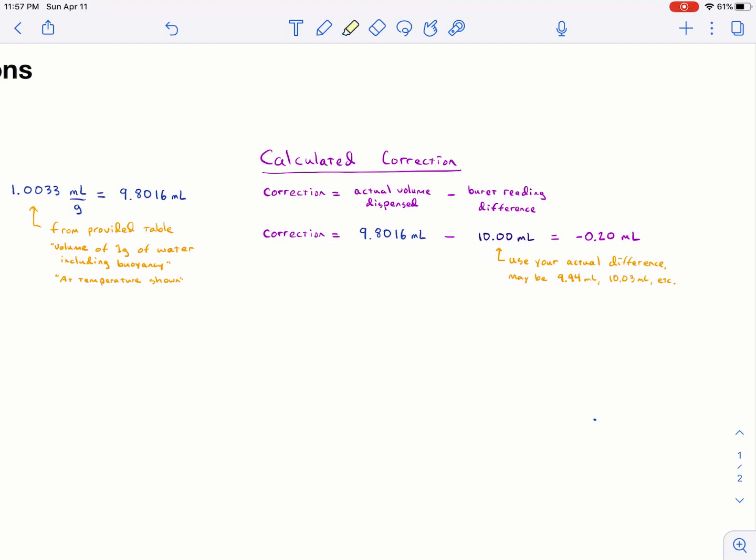When we calculate the correction, this just comes right over here. And this is the volume of water we actually dispense from the mass. And then you subtract from it your burette reading, use your actual reading, you might not have dispensed 10.00, you probably dispense something close to that. So use whatever that number is. And then you get your correction. Mine's negative because we dispense less than we thought we should have.